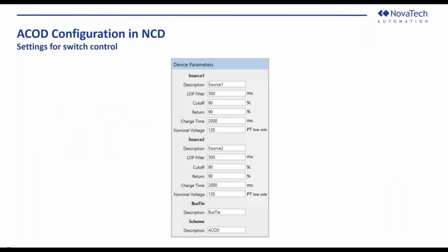Okay. So I wanted to say a little about actually configuring the parameters that the ACOD logic is going to be following. This is what you would see in the NCD screen, looking at the ACOD logic. You have an option for a descriptor for source 1, source 2, and also the bus tie down there as well. In the existing design, these names would show up on the little screen on the keypad there. Otherwise, they could be on the HMI screen for the updated design.